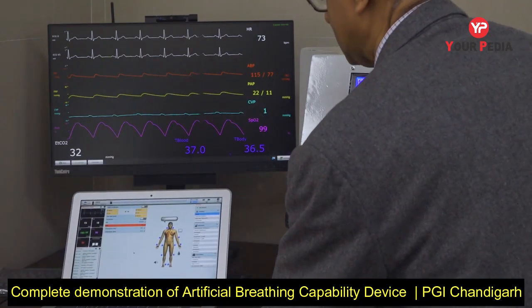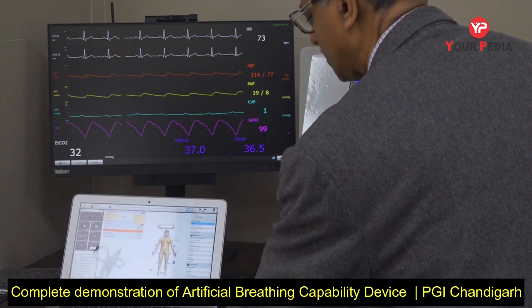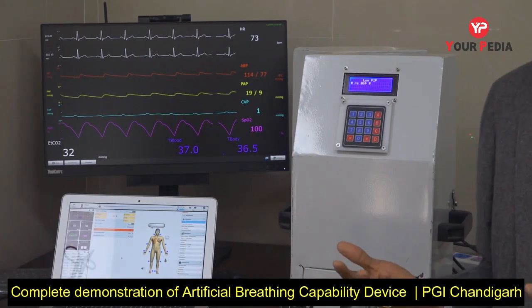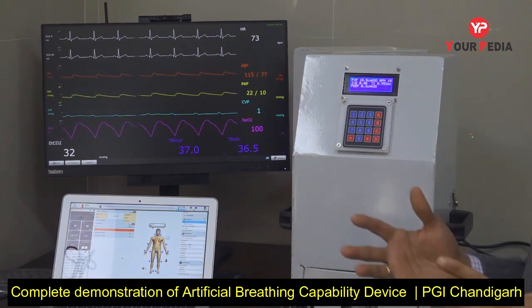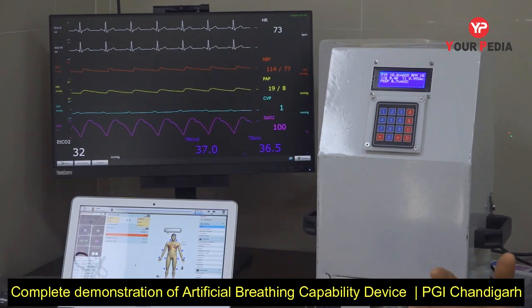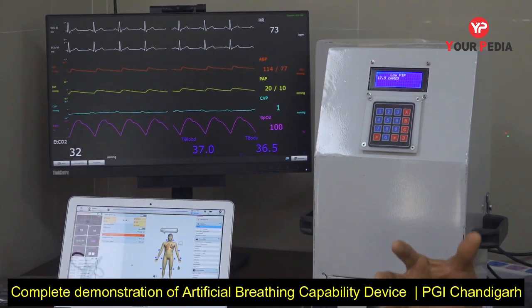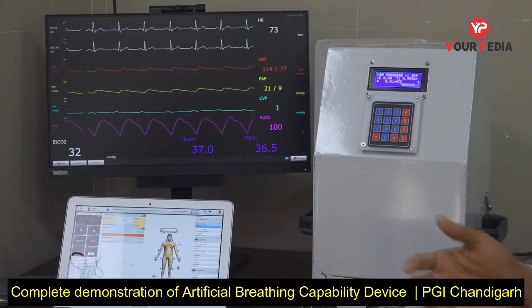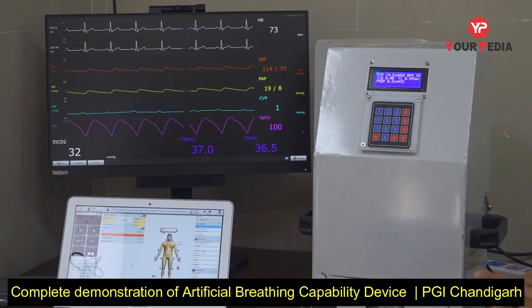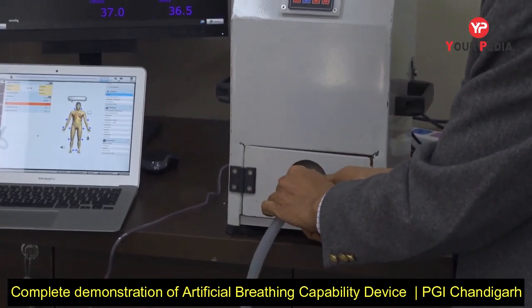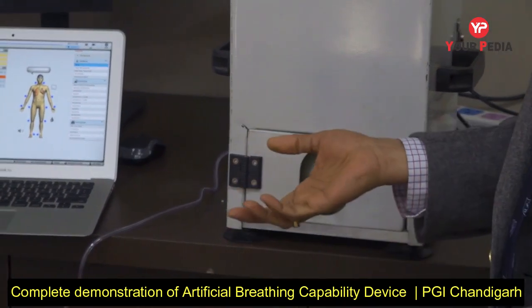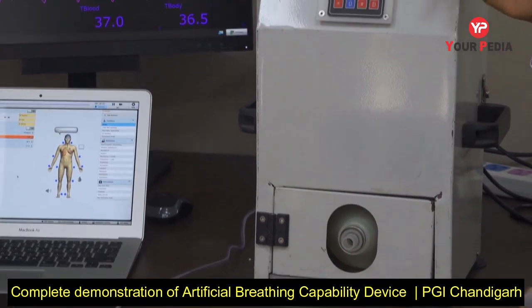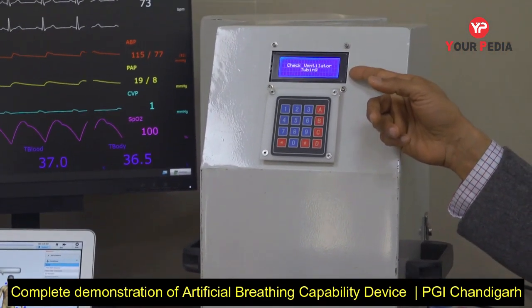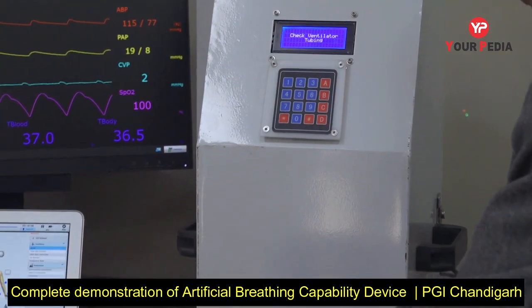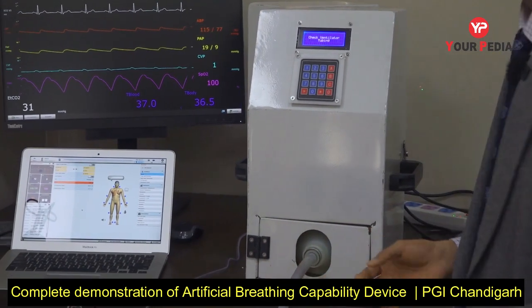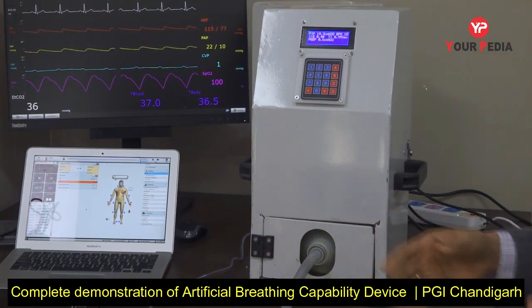Besides this kind of efficacy, we also have certain novel features in this device in terms of patient safety. One of these patient safety features is the cough alert. If the patient coughs when the machine is trying to deliver air into the lungs, the machine senses that, it will auto cut off for a preset period of time and then auto resume with whatever settings were instilled by the user. Now here I'm simulating a situation in which there is a disconnection in the ventilator tubing. When the ventilator tubing gets disconnected, the pressure sensor here picks it up and immediately shows, check the ventilator tubing. When patients are being ventilated by hand, this kind of safety is not available, and sometimes the patient gets compression of the Ambu when the circuit itself is incomplete.